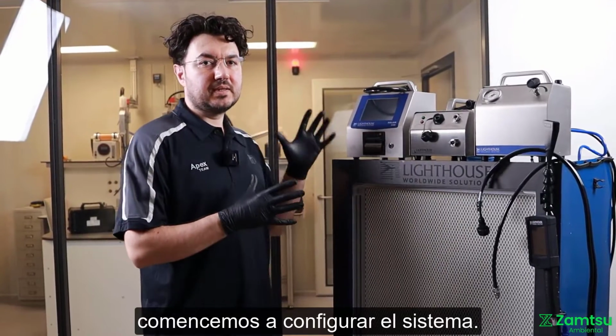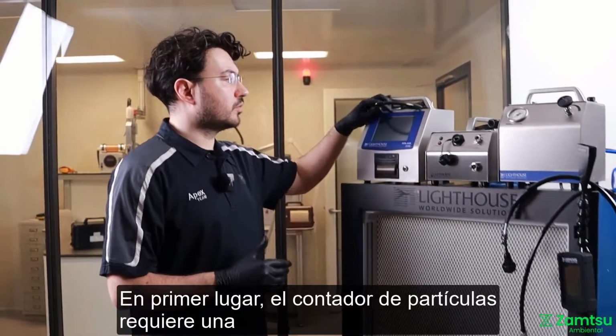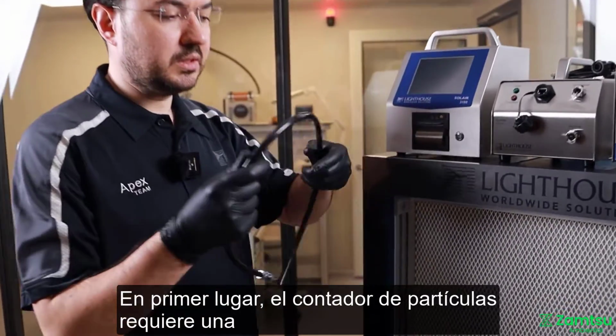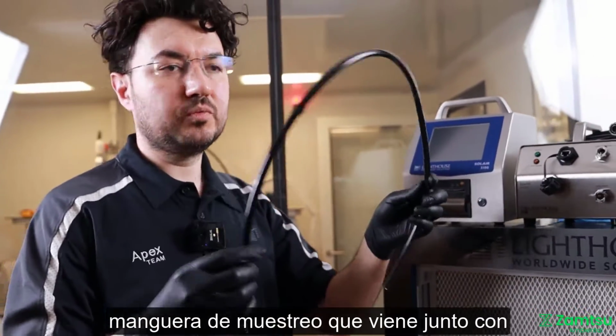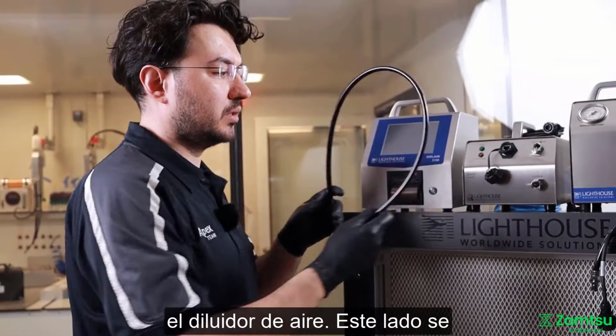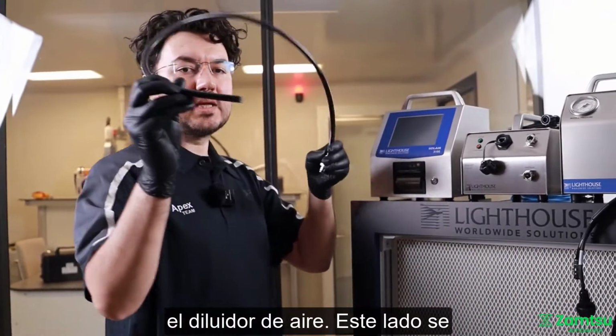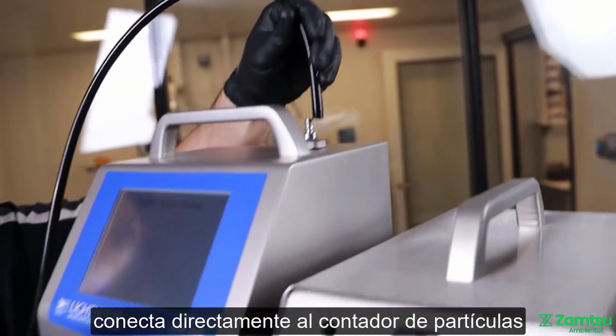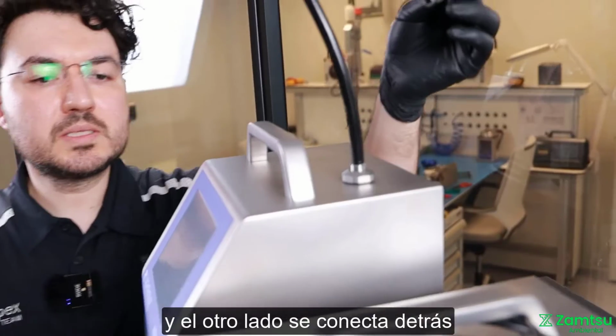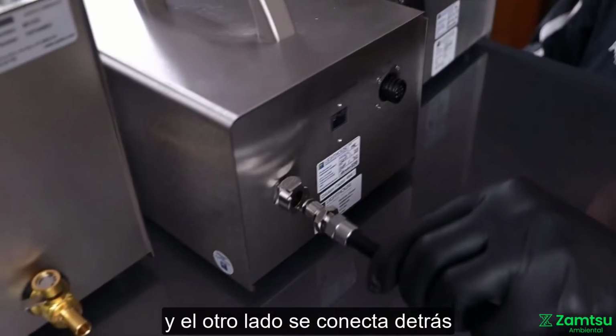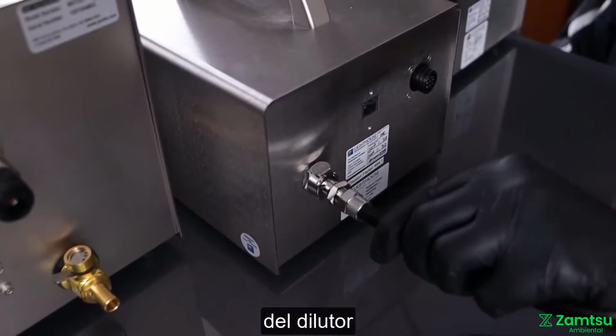Let's start setting the system up. First of all, this particle counter requires one sampling tube which comes together with scanner diluter. This side directly connects into the particle counter, when the other side connects behind the diluter.